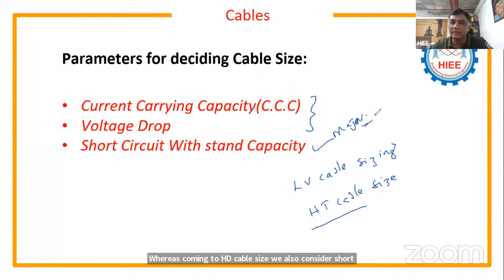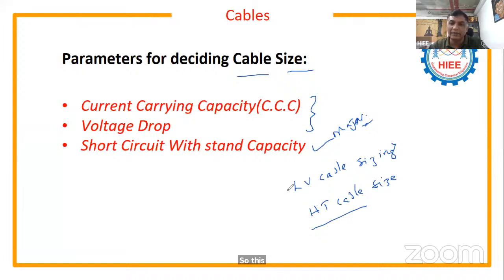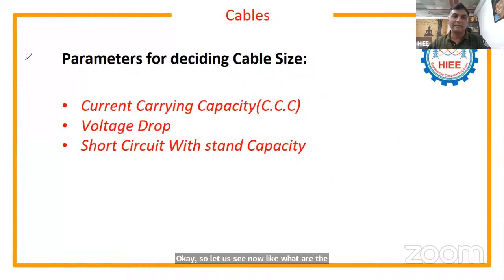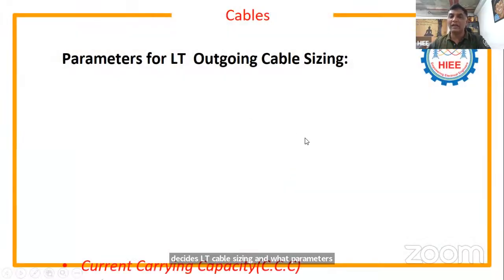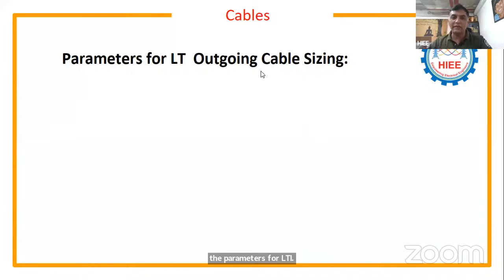Because when your voltage level increases, your fault level increases and your current carrying capacity will decrease. So this cable sizing calculation shall be divided into two parts: LT cable sizing calculation and HT cable sizing calculation. Okay, so let us see now what parameters decide LT cable sizing and what parameters decide HT. In the LT also you have different parameters. For example, if this is your SLD, these are all the outgoing feeders.